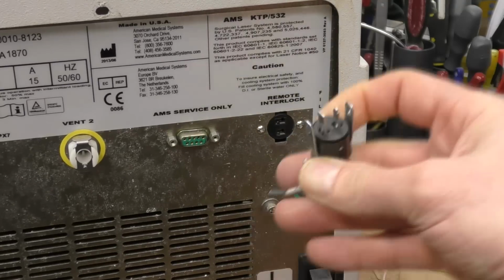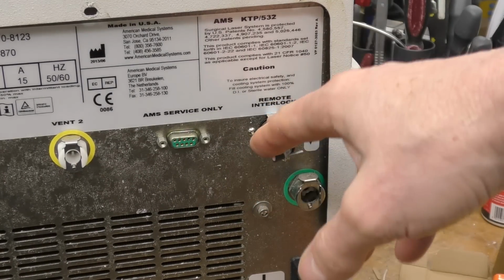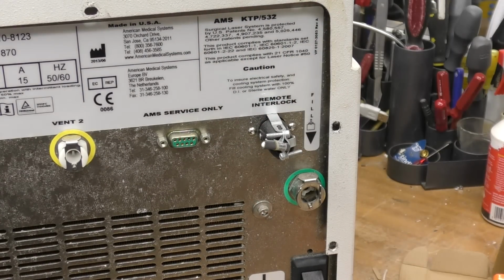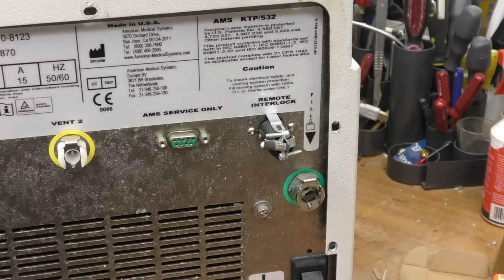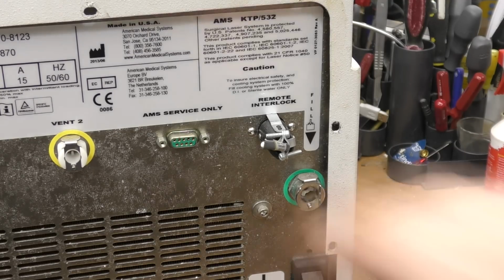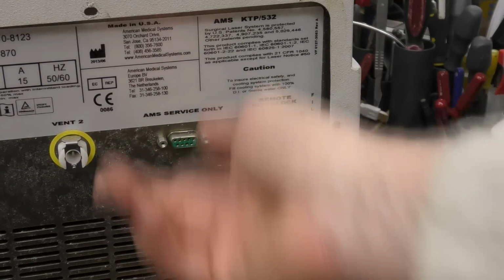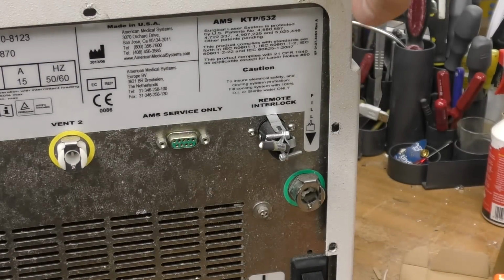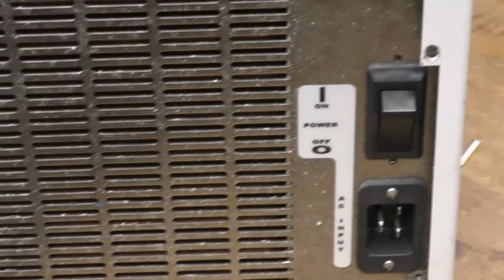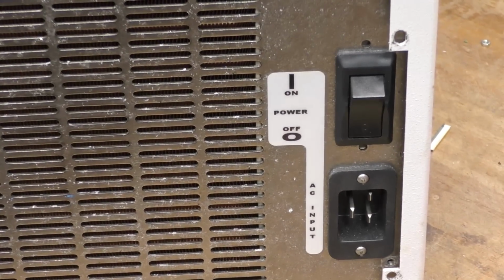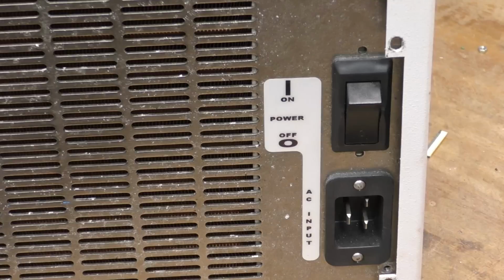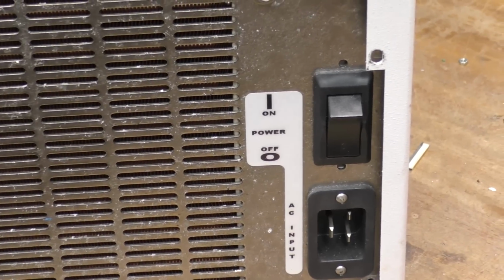Remote interlock. And that'll be used, for example, perhaps connected to a door switch on a room where the surgery was being performed, to shut the laser off if someone comes in. There's a service port. I think this has some sort of dongle that plugs in to enable service functions, which unfortunately I don't have. It's got the IEC 16 amp mains in that. The power rating on this at 230 volts is 15 amps.